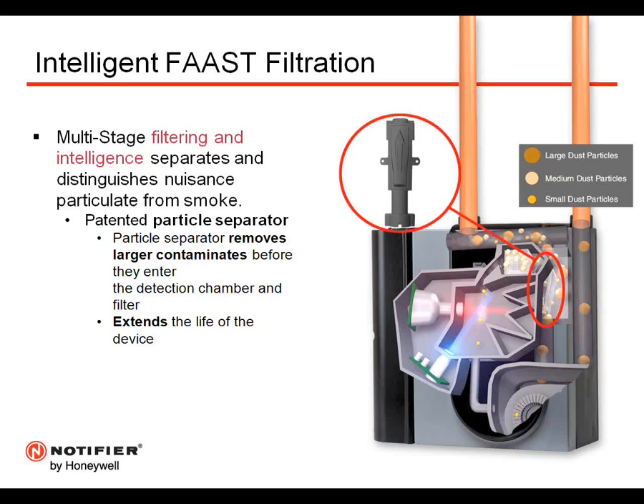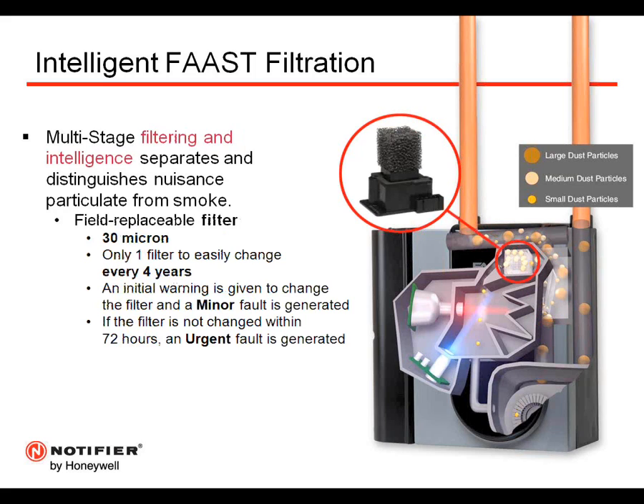This will effectively extend the life of the device, it extends the life of the filter, and ensures that there are reduced false alarms due to nuisance particulate. The second stage in our filtration process is a 30 micron replaceable harsh filter. This filter is, as I said, field replaceable. It just takes two Phillips head screws. This filter is also monitored, so if and when it does become clogged, the device will initiate a filter fault. That filter fault will be a minor filter fault the first time it's given, and then 72 hours later will be an urgent fault, identifying that the filter must be changed.